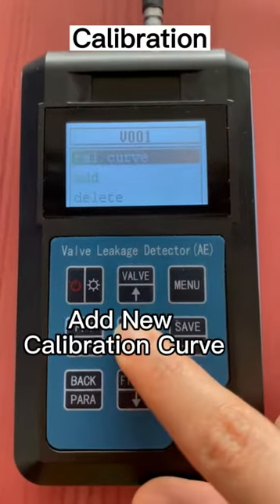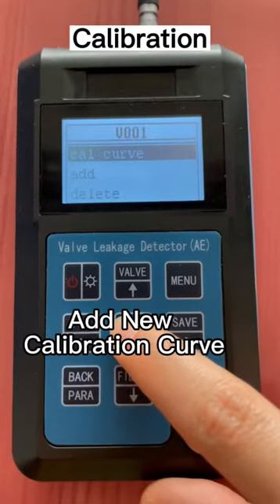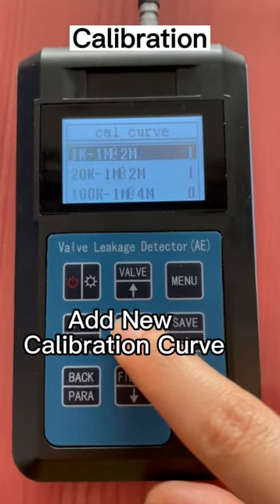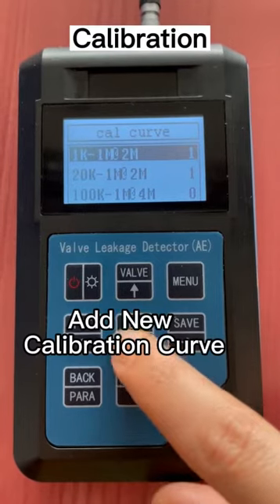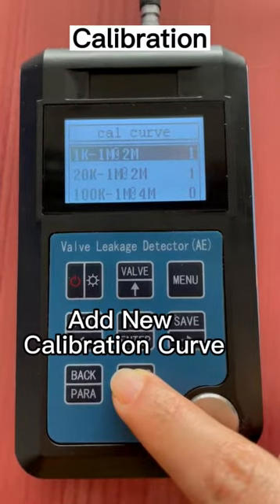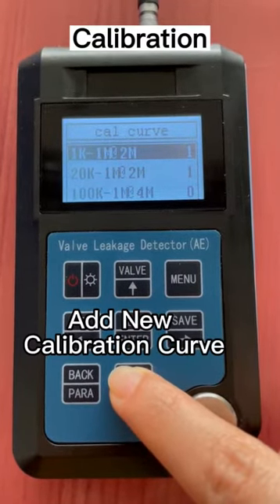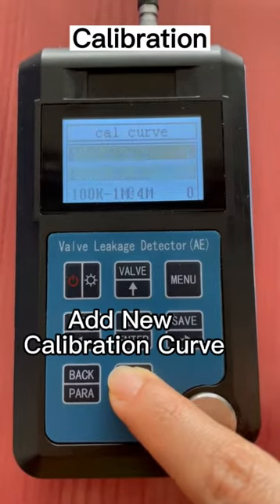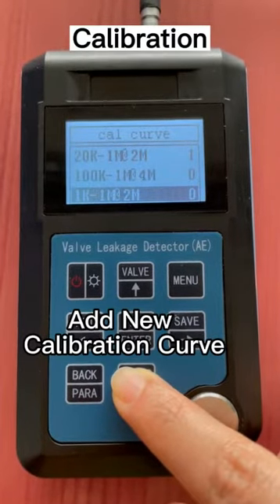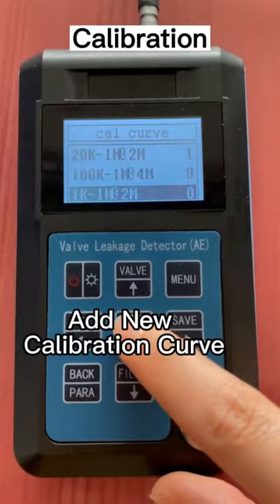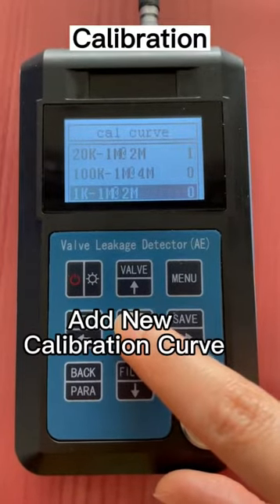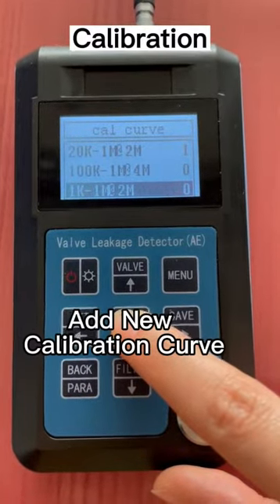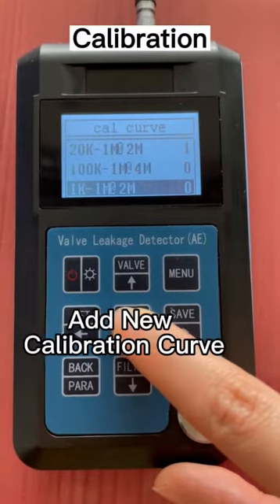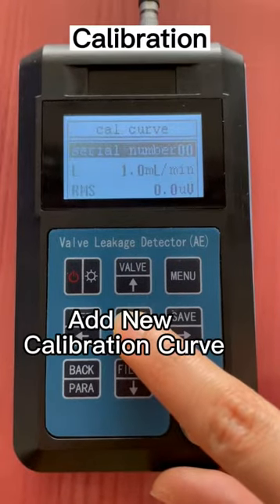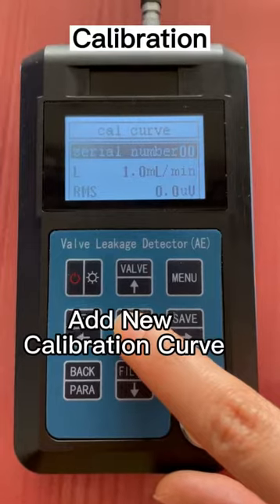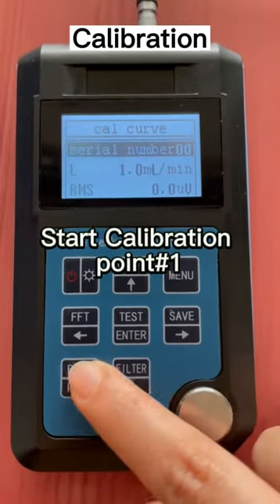Go to Cal Curve to start calibration. Select your desired sample rate and filter. For example, we choose the 1 kHz to 1 MHz filter at a 2 MHz sample rate. Press Enter to get into the calibration page.